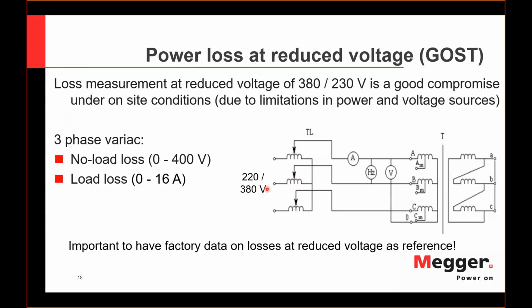Power loss test is again very popular in certain countries and given by certain standards. In this case, we accommodate a special three-phase voltage source, so a variac that can regulate the output voltage from 0 to 400 volt or output current from 0 to 16 ampere, three-phase. And we can connect a watt meter in between and see what losses, or let's say what power is being consumed by a no load test or a load test on the transformer.